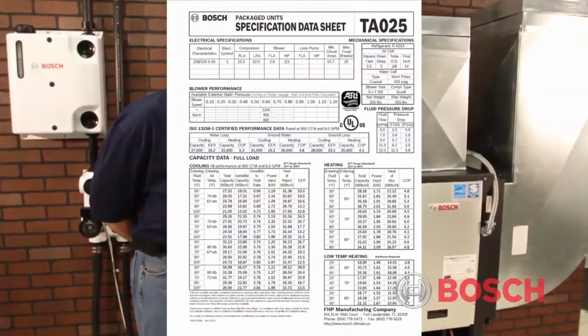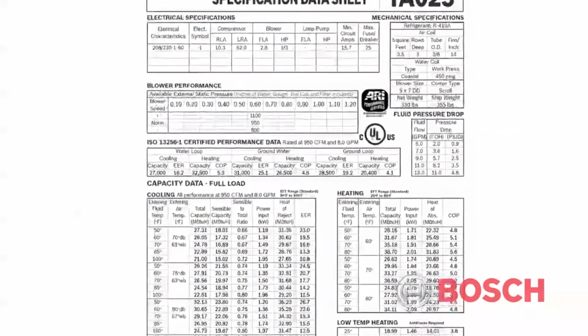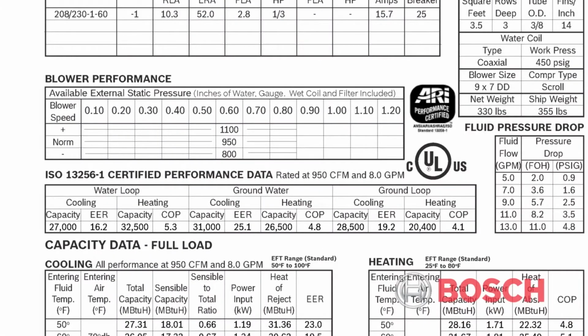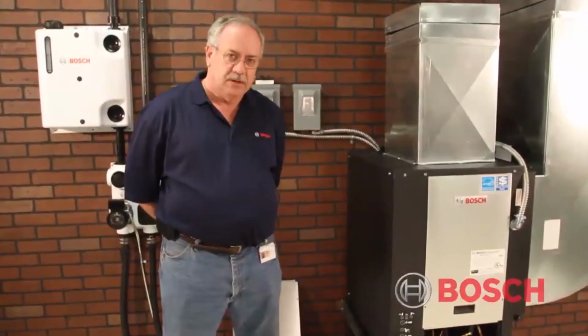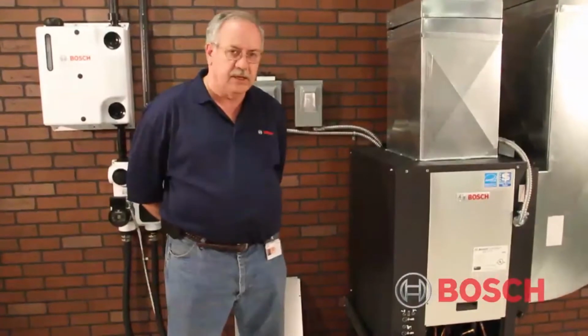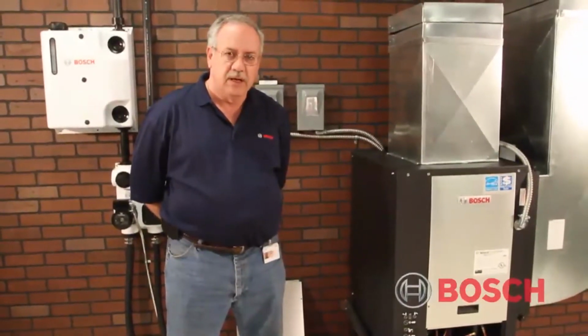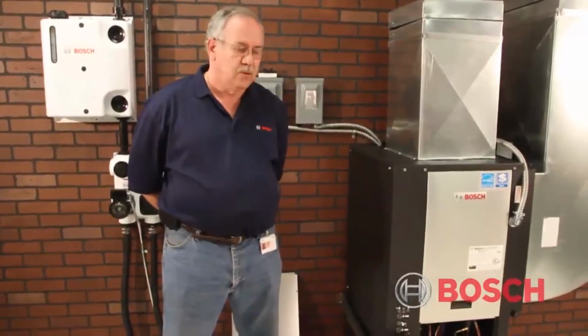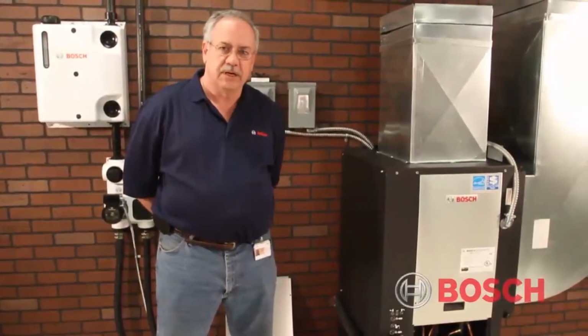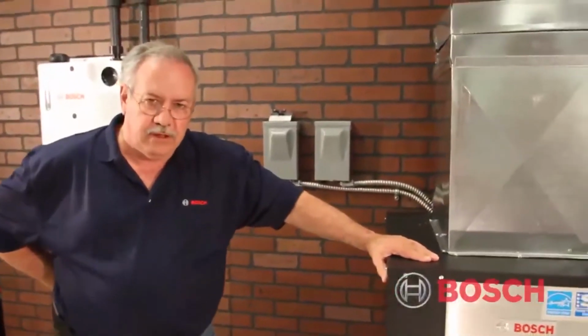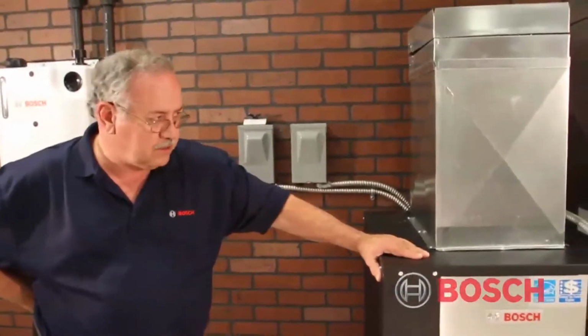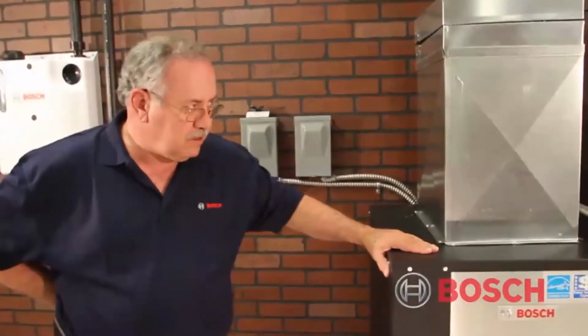If we refer to the specifications for the TA025, the blower performance data will indicate that this machine is rated at 0.6 static pressure and functions at about 900 CFM. So we can assume that is correct in the field if the ductwork is designed properly. But when you're out in the field and you want to check the airflow, the simplest method when we have a heater installed is to do temperature rise across the heater.